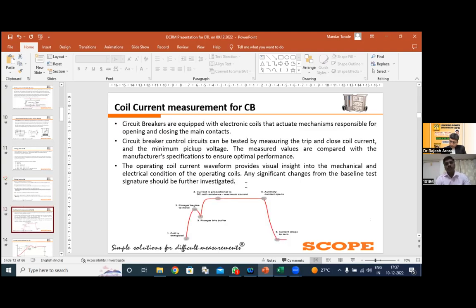Moving further, the coil current measurement test. As all of us know, what is the purpose of the coil? The coil is basically used to actuate the mechanism. What we are doing is extending the positive DC. Always the negative is available at one side of the coil. And whenever required, we extend the positive to the coil through the auxiliary switches. So the purpose of the coil is to actuate the mechanism. Once the coil is energized, it hits the plunger, the latch gets released, and the mechanism starts moving.